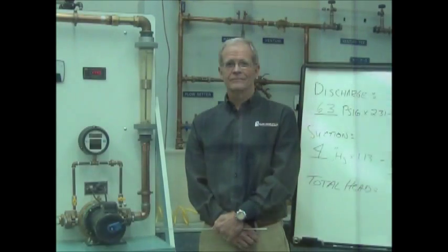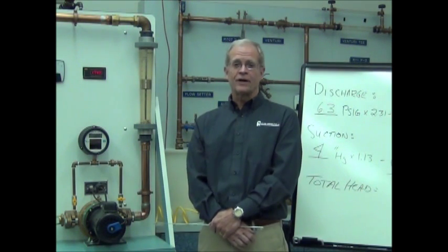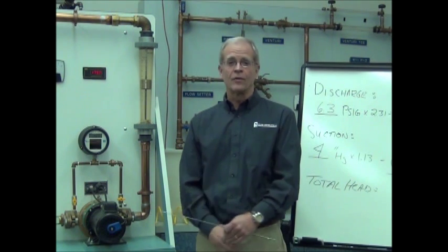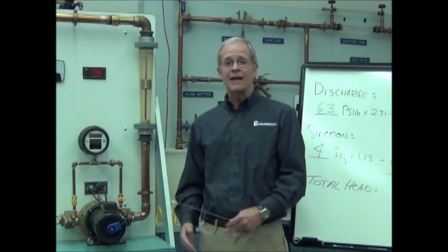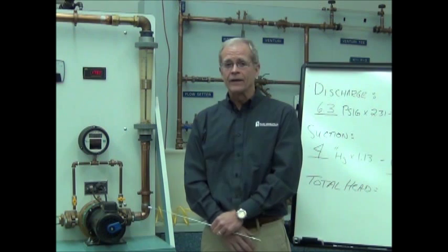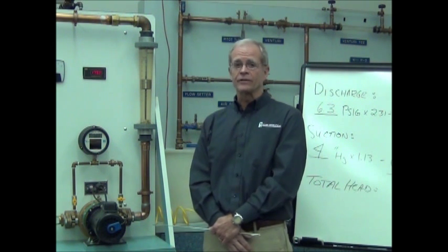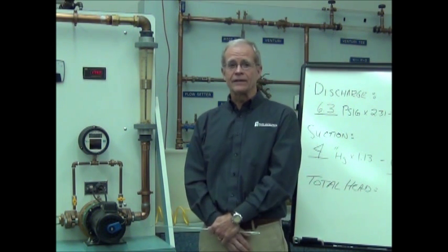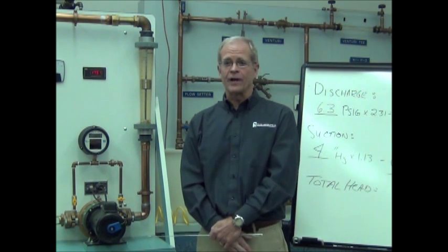There are many times you may find yourself in the field wanting to know what the flow is from a pump and not having a flow meter like we have here. I think we've shown that using a good quality gauge and pump curve, we can come pretty darn close to determining what the pump flow actually is.